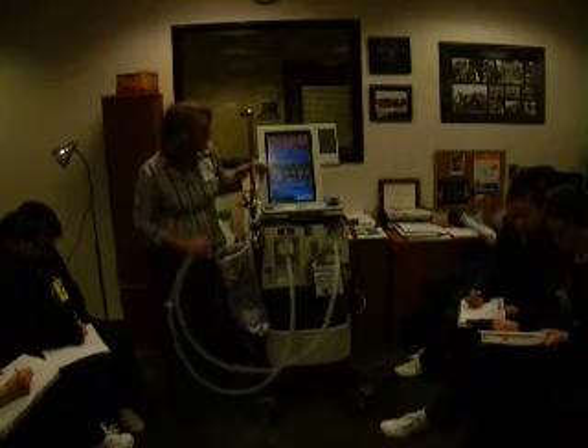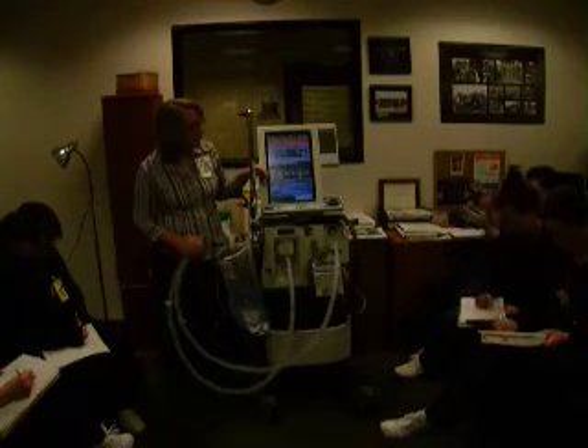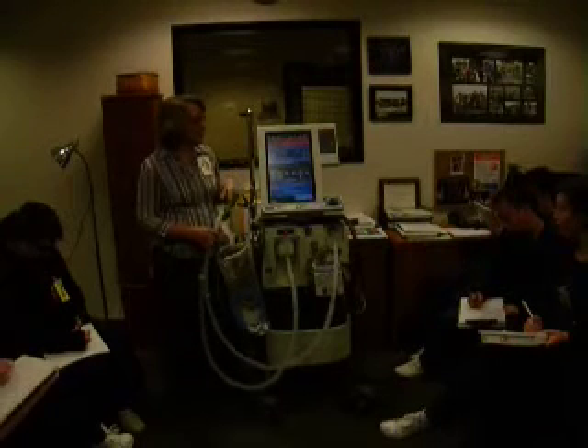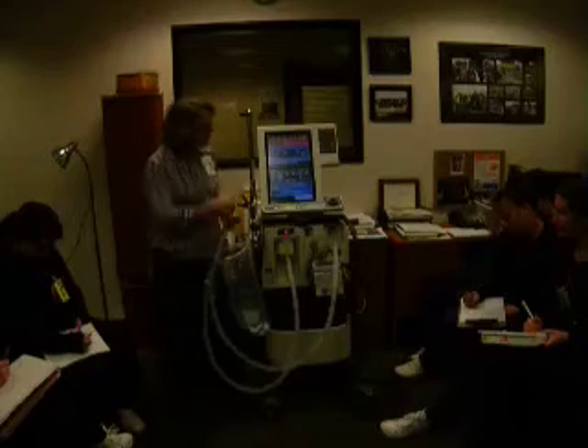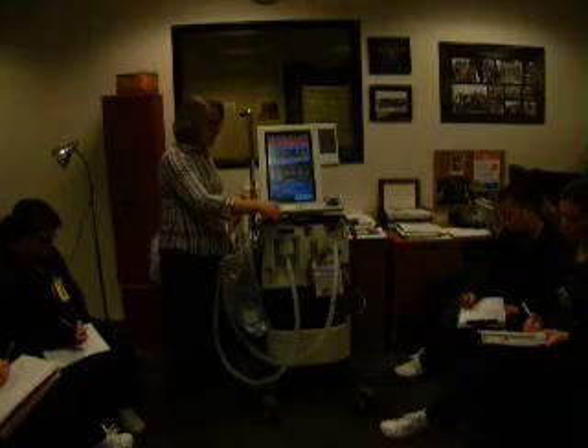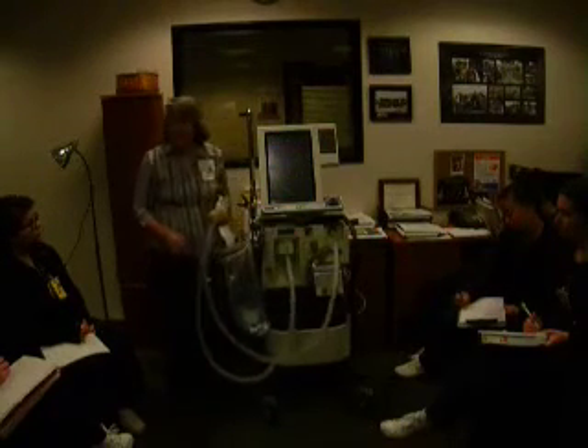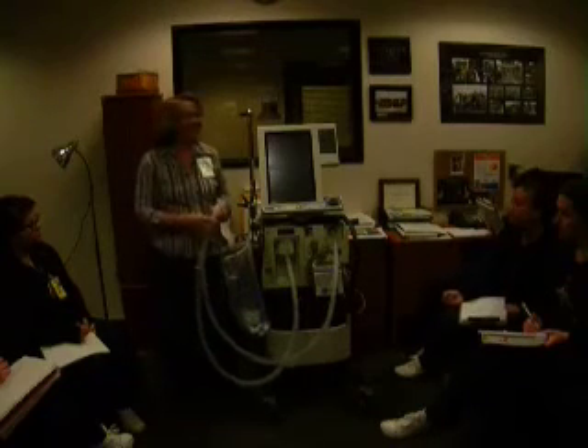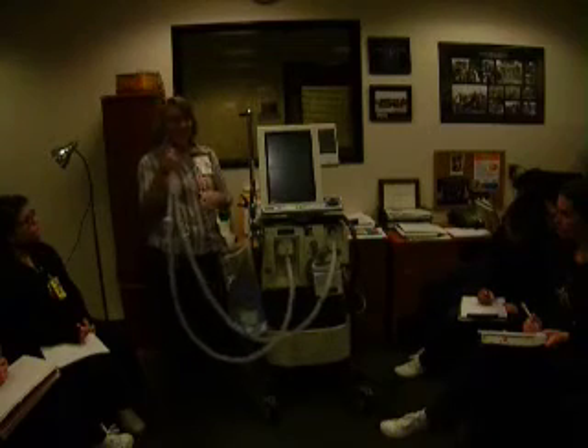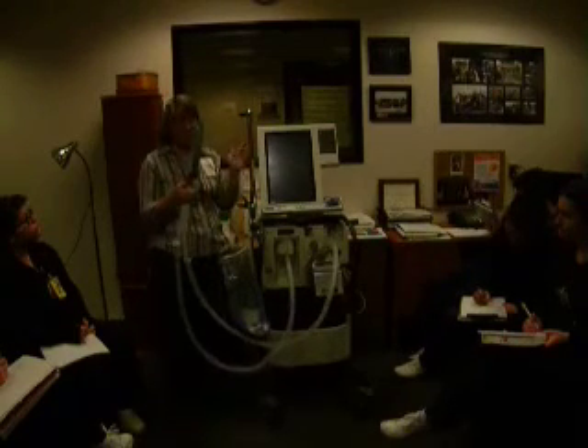Isn't it similar to that? You have to do a sensor calibration before you even hook up the patient. Well, you have to have the sensor on there, but it won't do what this thing does. This thing goes nuts. And you see that this is going to give you crazy alarms. It's going to go into what's called safety ventilation, one alarm after another. And you have to shut it off and start over again when you do that. So if you turn on your ventilator and do this at any point before you set your settings and confirm them, you're going to have that happen to you.